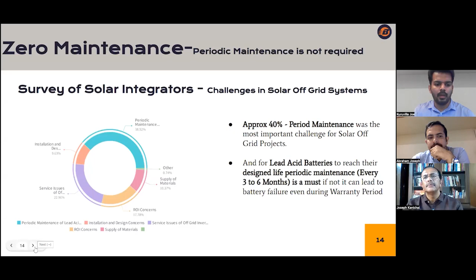The next important point is the full load ability of these batteries. One limitation of lead acid batteries is that as the load increases, the performance or backup time comes down drastically. For example, a 12 volt 100 Ah lead acid battery might give more than 2 hours at 40 ampere discharge, but if the discharge current increases to 80 ampere, performance degrades drastically, and you may not even get 1 hour backup.